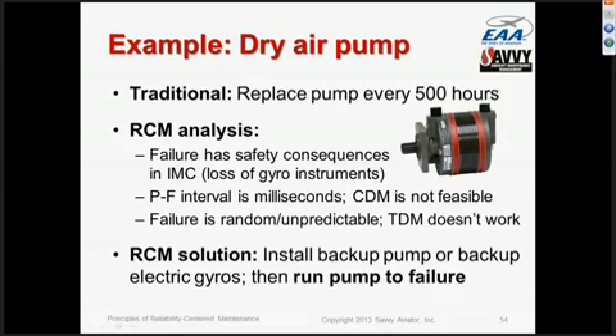There are all sorts of theories. They have these inspection ports and stuff where you can inspect the vane length. But having studied this situation for about 25 years, I can tell you that vacuum pumps fail when they want to fail. They give you no warning. The pump runs absolutely perfectly right up until it doesn't. And then in a matter of milliseconds, in a big puff of broken vanes and graphite powder, the pump suddenly becomes inoperative. Failure is random, unpredictable.